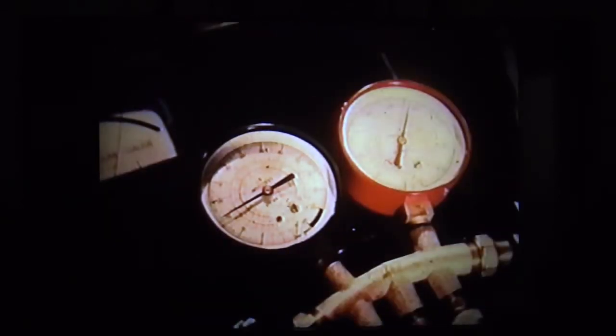Read and record the pressures registered on the manifold suction and discharge gauges. Refer to CTS 2622M for correct pressures. Pressures will vary according to ambient temperature as indicated in the performance chart.